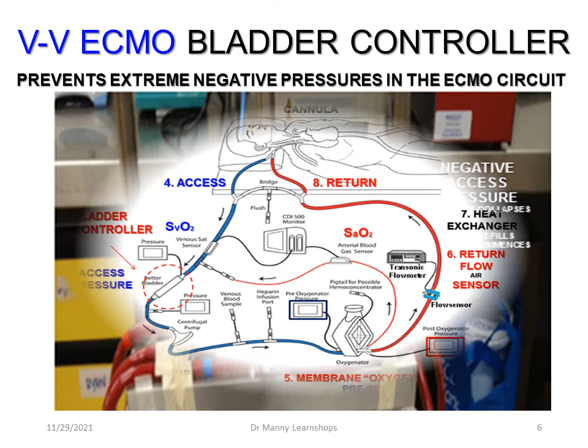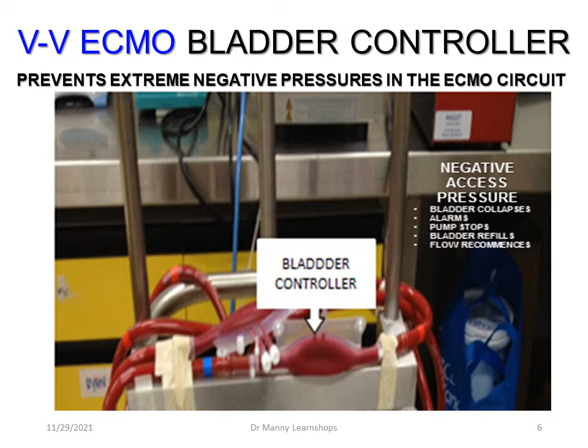Now, as I said, the bladder controller prevents extreme negative pressures in the ECMO circuit because negative access pressures cause the bladder to collapse. It activates an alarm. The pump stops because you don't want extreme negative pressures in the circuit. Then the bladder slowly refills if the problem's been corrected and flow recommences. It's an important safety device.